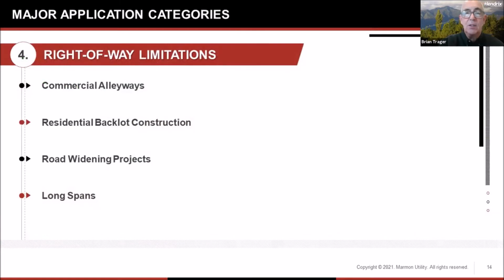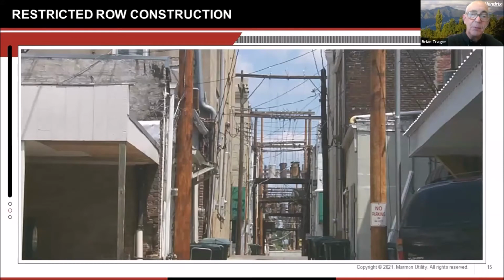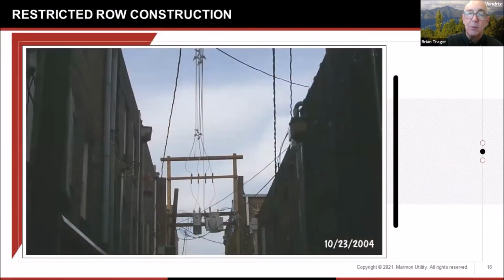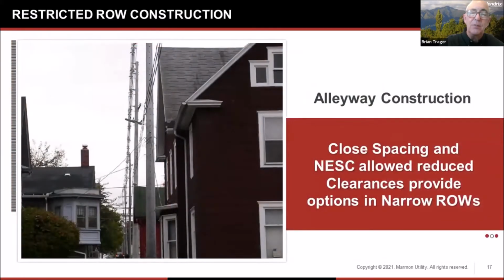Couple of other applications: commercial alleyways, backlot construction, road widening. Here's a typical situation, and this is commercial, but this could be industrial as well. You've got a 5 to 15 or 25 kV upgrade. National Electric Safety Code, or CSA, you can't fit it in the alley once you go to 15 kV. So you just install spacer cable. And we've got, you know, lots of these projects. Here's a substation exit. We're going down a residential alleyway. The only way you can do that is underground or with spacer cable.